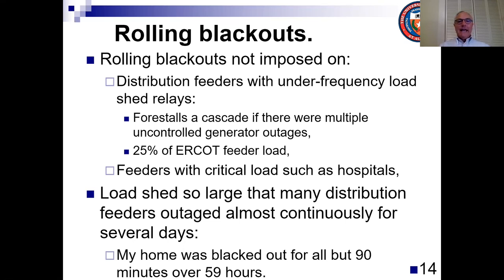The first is that there are distribution feeders in ERCOT - distribution being the wires, typically radial, that do the last few miles of delivery to consumers. Distribution feeders have so-called under-frequency load shed relays. The idea is that if there were multiple uncontrolled generator outages, the electrical frequency would drop as supply dropped compared to demand, and these under-frequency relays would trip. So 25% of ERCOT feeder load is on under-frequency relays. That's our last-ditch defense against a cascade that would cause a complete system blackout. So we're not going to impose rolling blackouts on those loads because we need them just in case.